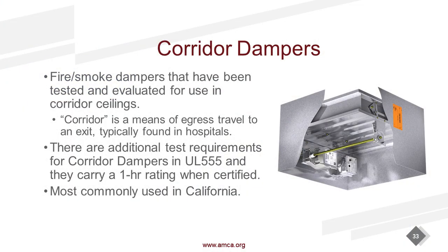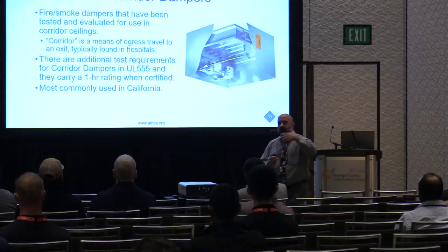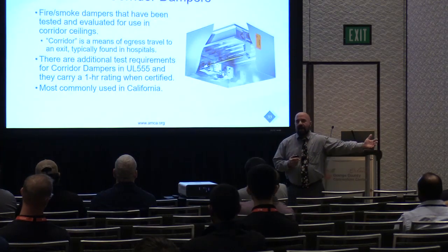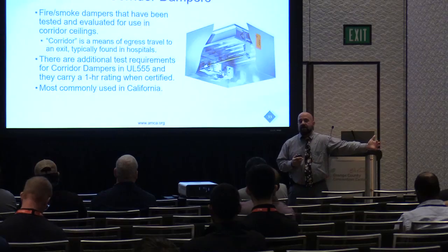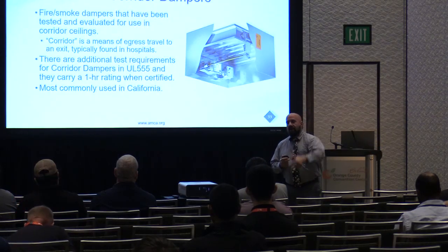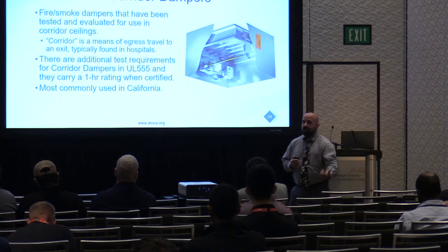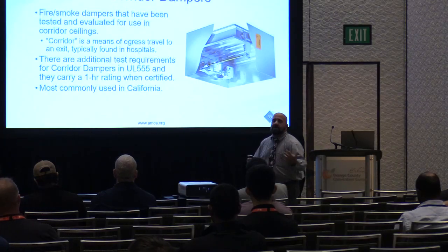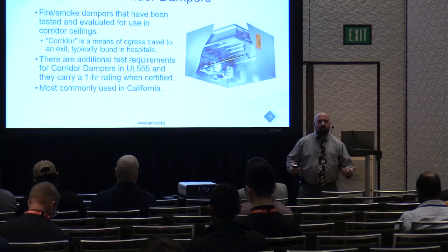I already spoke about corridor dampers, so I won't repeat that, but again, it's just a special type of fire smoke damper, and I bring them up more and more. Building codes are what? Absolute minimums. They are the least you can do to make your building safe. There's nothing saying you couldn't add dampers to provide a safer building. What we see is a lot of designers from the West Coast, from events that happened in this country in the last couple of years, have decided to leave California and take their best practices with them. That includes inspectors, that includes installers. So we're starting to see corridor dampers pop up in drawings all across the country now.